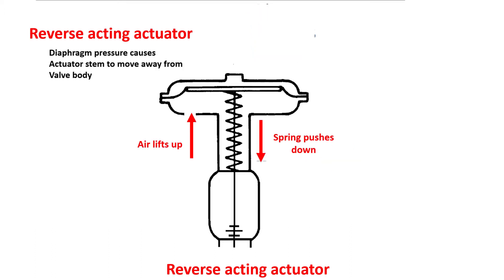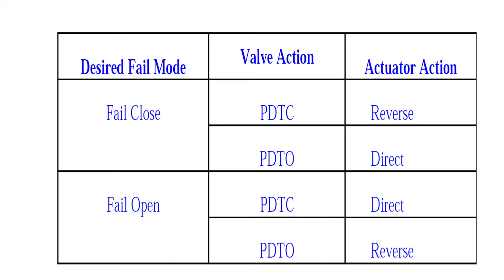In a reverse acting actuator, the diaphragm pressure causes the actuator stem to move away from the valve body. So to summarize: in a direct acting actuator the diaphragm causes the stem to move towards the valve body, and in a reverse acting actuator the diaphragm pressure causes the actuator stem to move away from the valve body.